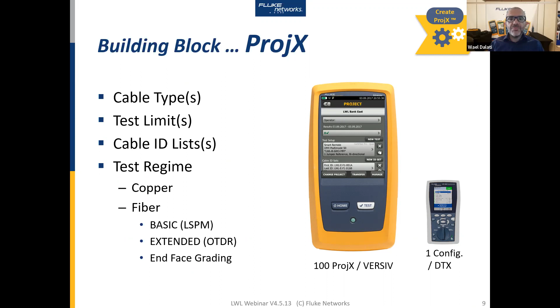Unlike our old DTX, which is no longer in support or production—so good, I'd say farewell to it—it used to have only one configuration. Every time you needed to change, you had to reset the whole configuration, move by move. While on the Versiv, we have 100 projects where you allow the technician, when moving between projects, to simply change the project with a fingertip, and then you're set to go for the next project.